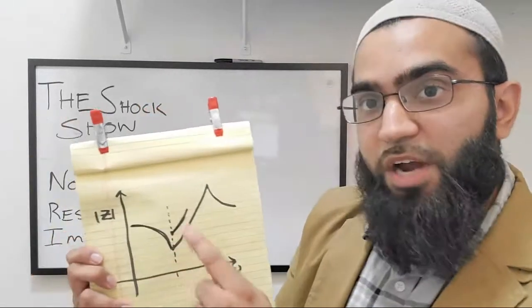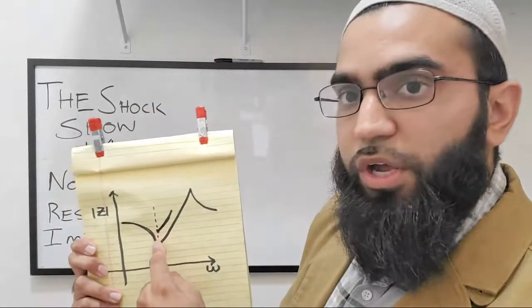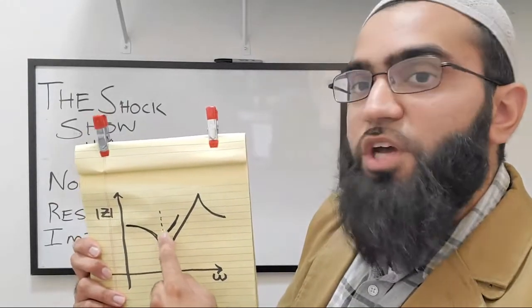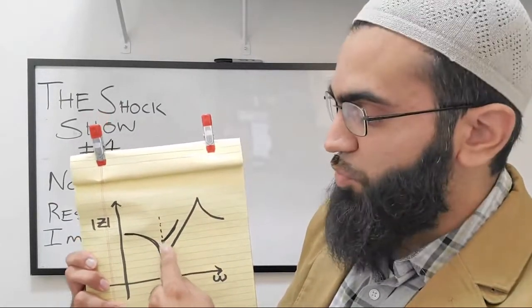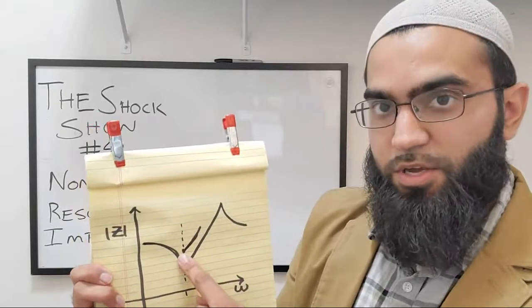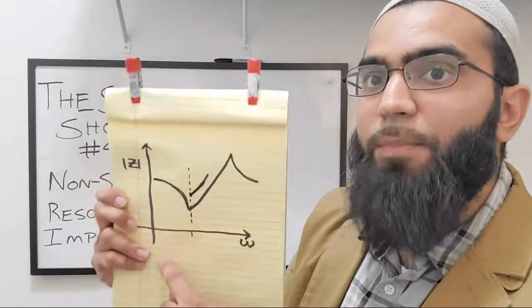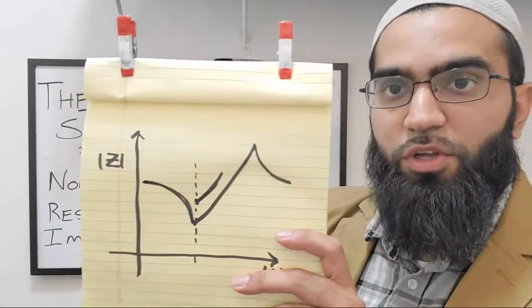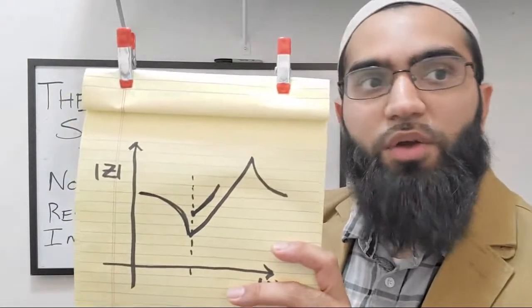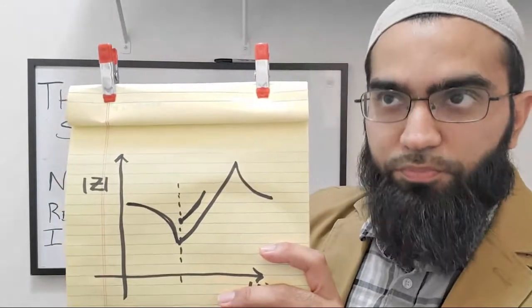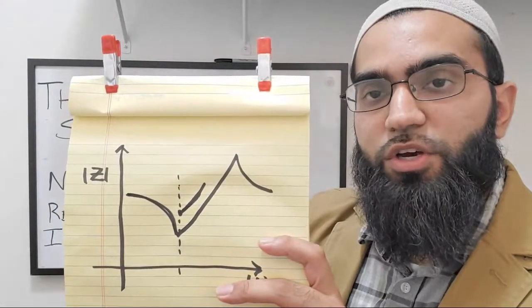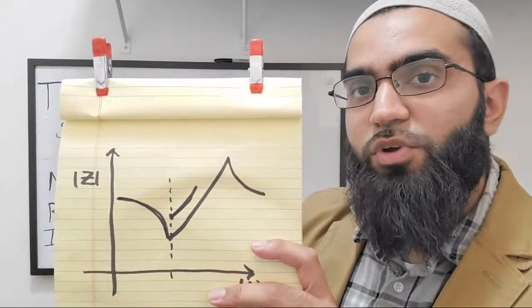It also happens at higher voltages. You'll get discontinuities happening. So this becomes really challenging to analyze and pursue. It's important to recognize this and why it's happening. It's not necessarily because you're doing the measurements wrong. The way to correct for this is actually to have a method of current limitation. And intrinsically, impedance analyzers do have a finite output impedance.